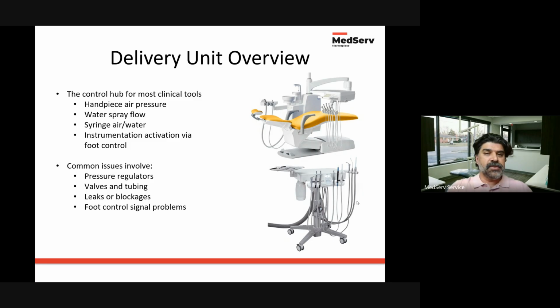In addition to the chair itself, another unit in the operatory that typically has some common issues is the delivery unit. You can either have it attached to the patient chair, as can be seen, or there's a separate portable unit available. This is essentially the control hub for most of the clinical tools used there. It regulates and routes compressed air, treatment water, as well as vacuum suction.